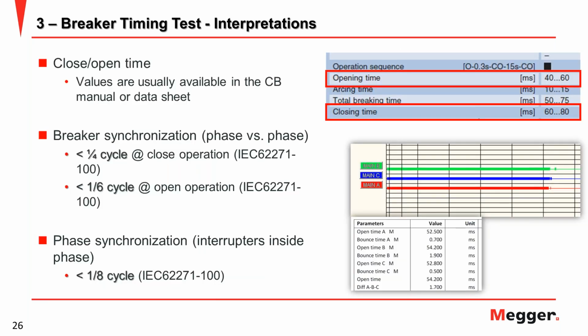And for interpretation, there are many standards, but mostly we use the IEC 62271-100. If you don't have the information from the manufacturer of the CB, you will mostly find it on the datasheet. You can find it on the website or on the datasheet of the breaker. Usually they will provide this information. For example, this is one type of breaker.